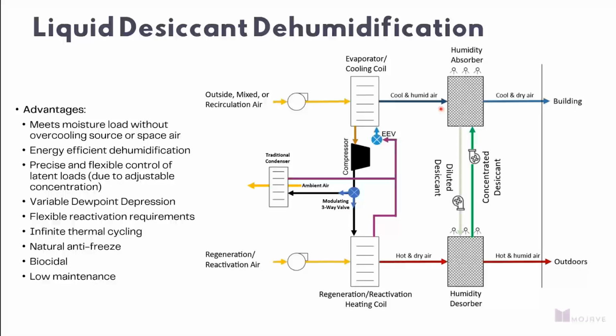So to say that differently, for every iteration of dehumidification, you get equal parts of heat associated with that released back into the air. So there's a conservation of energy happening. You're converting latent energy to sensible energy. So you actually get passive reheat as a result of this dehumidification process. So going back to high school chemistry days, you call this an exothermic reaction. So to summarize, as we come out of this absorber, it's doing dehumidification and heating, providing neutral air to a space, and this air can be anywhere from 55 degrees dry bulb to 75 degrees dry bulb, and anywhere between 35 dew point and 55 dew point, and that's all actively controllable.